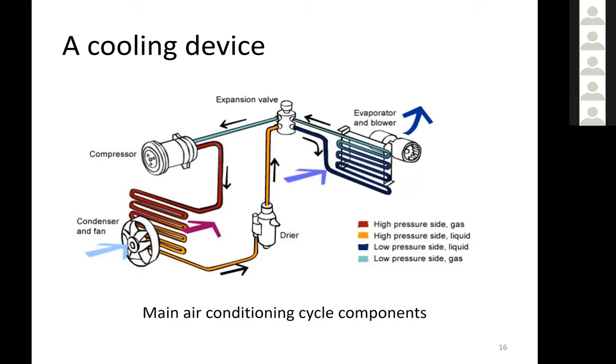So here you have basically the compressor. You compress the refrigerant, then it goes to high pressure in the vapor phase and high temperature, of course. Then with the surrounding, you're going to exchange heat. The heat goes to the surrounding, and that will basically make it high pressure, low temperature in the liquid phase. And then you go to the expansion process. With the expansion, you drop the pressure to low pressure.